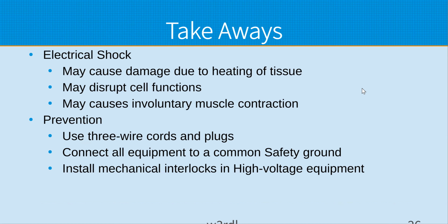Okay, so we learned that shock can cause damage due to heating of a tissue, which is a burn. It could disrupt cell functions like your heart muscle and interfere with the signal going to it. You can definitely get muscle contractions. I can verify that. You should use 3-wire cords and plugs and not one of these little cheap adapters. Try to connect everything through a low resistance wire to a safety ground, which is why copper strap or copper braid, because there's a large surface area and current actually travels on the surface of conductors. And have mechanical interlocks in high voltage equipment to at least turn the power off if you open it up.